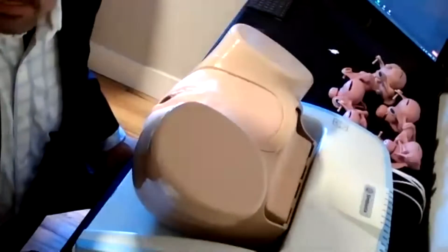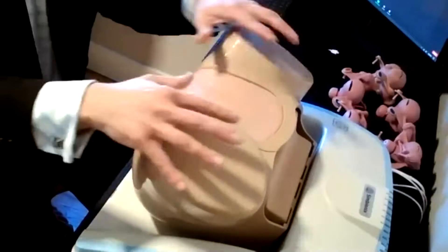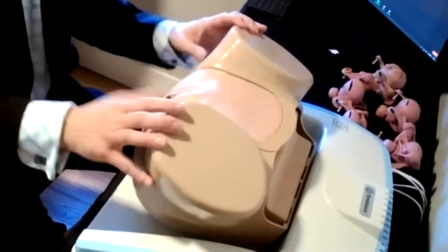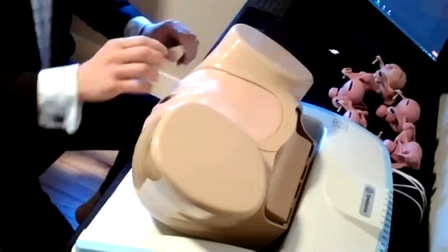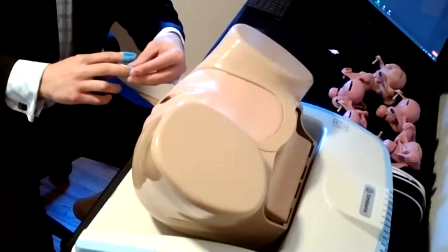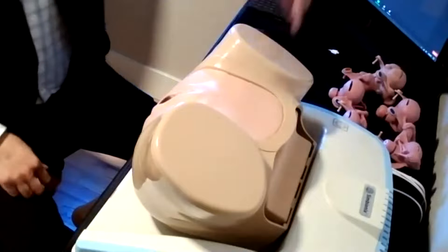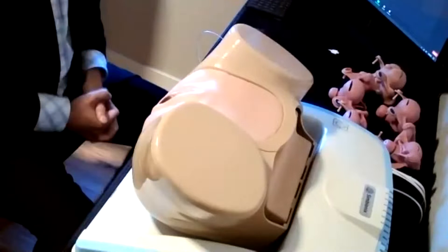This is the most important part of the simulator — a palpable mannequin which contains a lot of structures inside. We worked with quite a few doctors and nurses on developing a mannequin that is as close as possible to reality in terms of feel. Other than the palpable mannequin, we use finger sensors. I'll place the finger sensors on my fingers, then put a glove or the finger cots that come with the simulator, and my virtual fingers are going to physically palpate the mannequin. There's another box which connects everything together, turning the physical into the virtual you'll see on the screen.